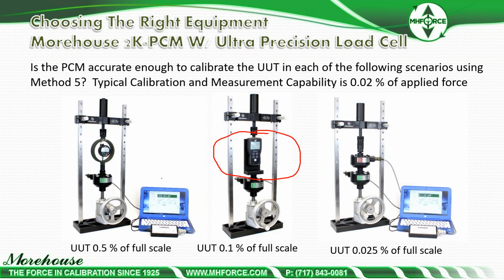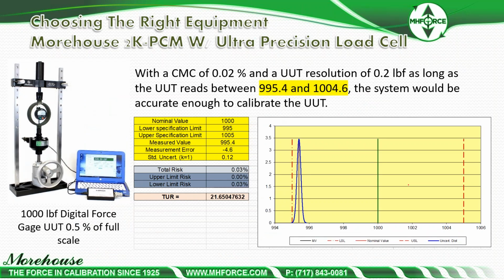But when we start looking at it, UUT of 0.5% of full scale, 0.1%, and 0.025, we're just going to start looking at what it takes to be in. So CMC of 0.02% and a UUT resolution of 0.2, as long as the UUT reads between 995.4 and 1004.6, the system would be enough. So that's a 0.5%. So we're looking for plus or minus, really plus or minus 5 pounds.